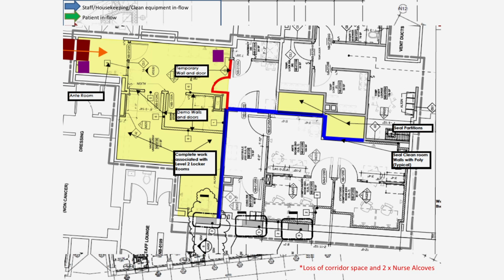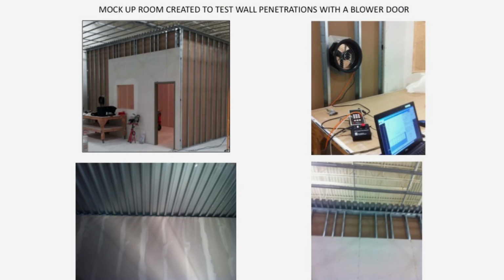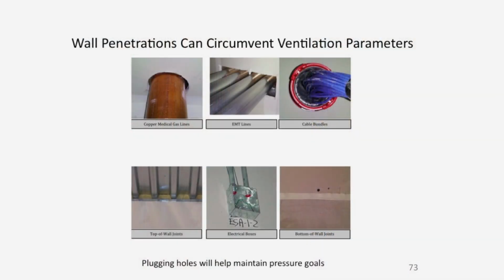So I see the problems we have at my institution if the space isn't well controlled. What we did was engage the Carpenters Union, and through the work of Hilti, we set up a mock room, built like any building would be, with holes from the upper deck to the walls, and from the floor to the slab below. We set up a blower door, our fan in the system, and tested a whole bunch of different penetrations that come through the wall in a typical room, no matter where you are in the world. These things come through your wall, and fire code, being the boss code, dictates that we seal them up.